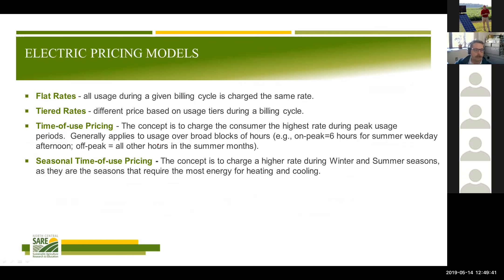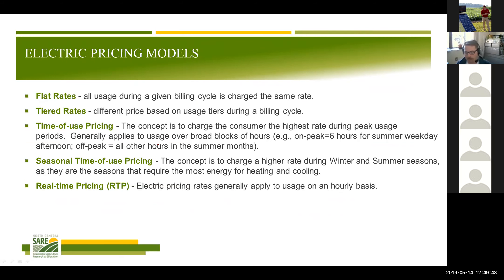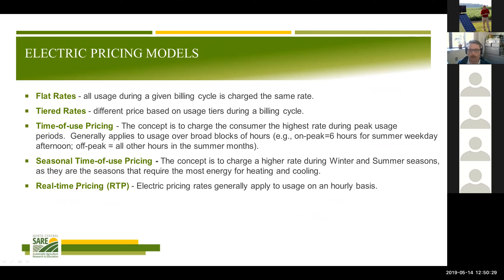There are lots of other rate schedules out there, and it's worth looking at different bills to understand what's available for your constituents or your particular business. These could be as simple as a flat rate for all time; tiered rates like summer/winter; time-of-use pricing with higher prices in the middle of the day and lower prices at night; seasonal time-of-use where only summer has time-of-use rates; and finally, real-time pricing where you're charged whatever the rate is on a five-minute increment.